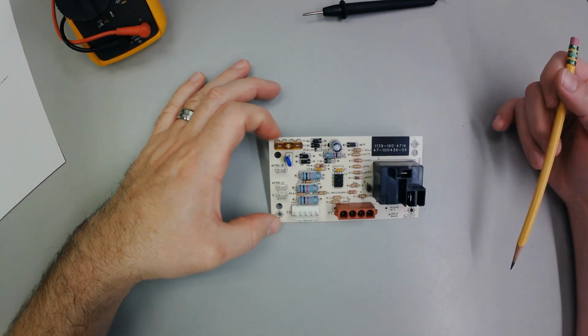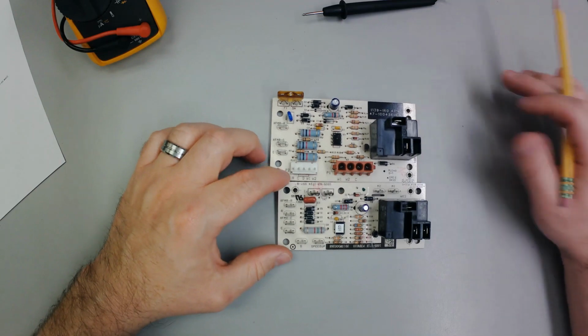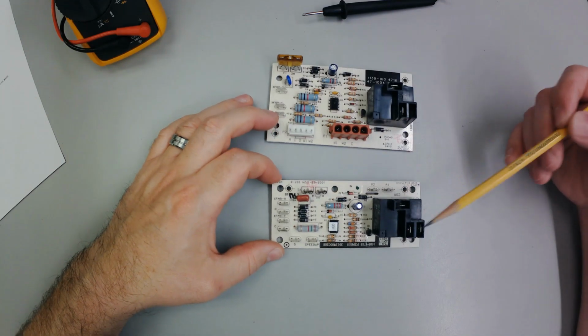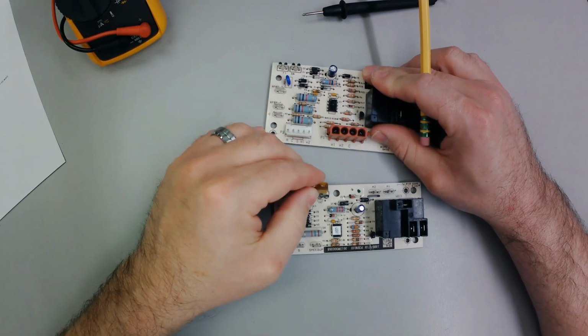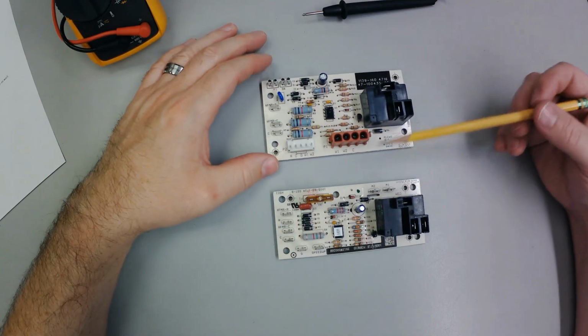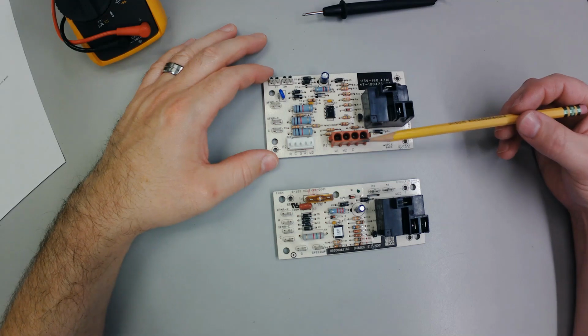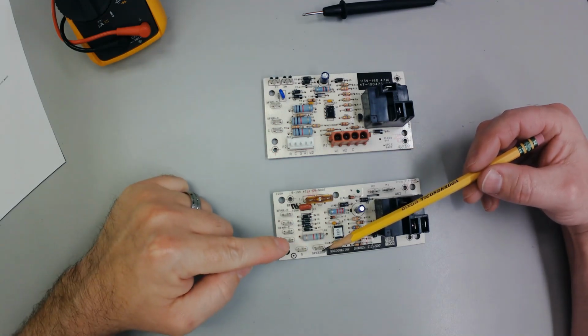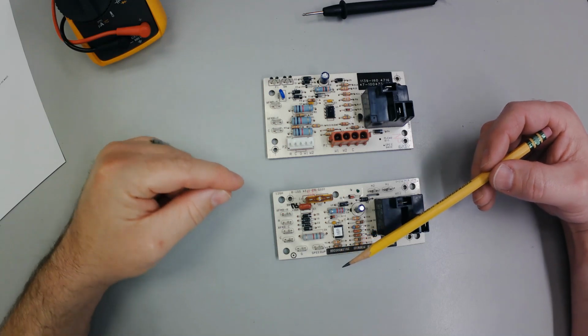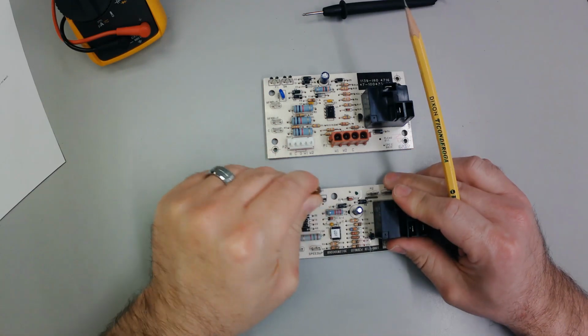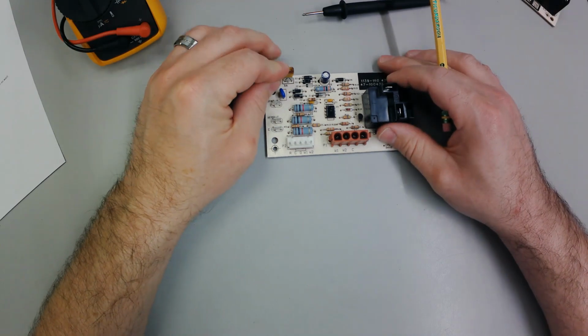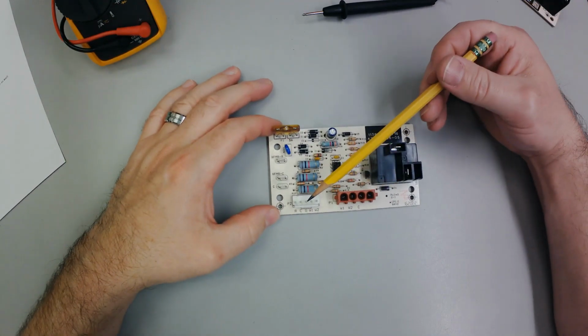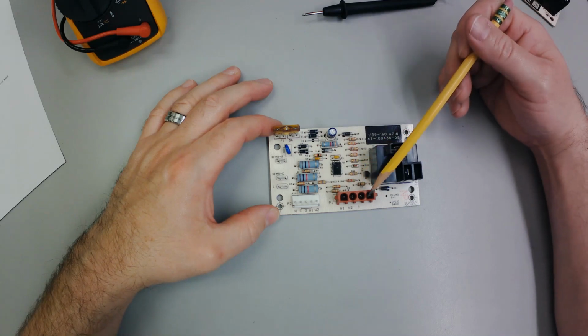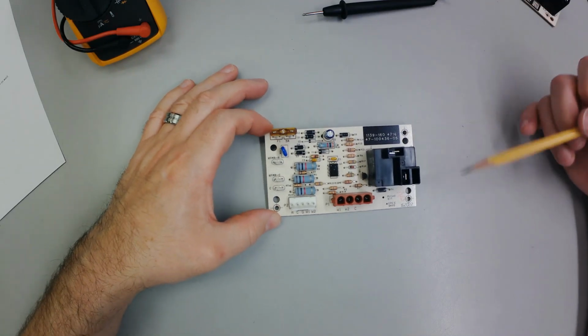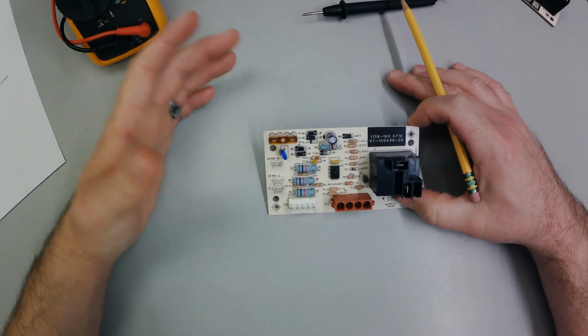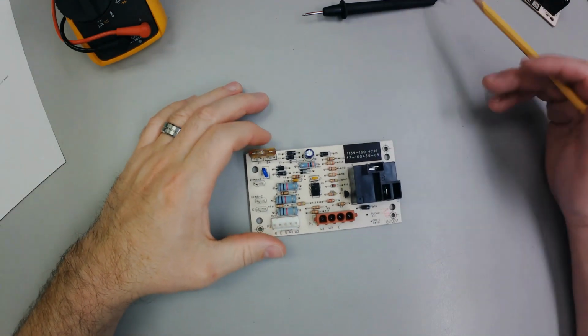The one thing that the Goodman board had, right? I'll flash it back real quick. On the Goodman, we got the relay, we got where the fuse goes, okay? But the Goodman board did not have these plugs soldered into it. We actually had some 1/4-inch male spades to connect to, and it was pretty much individual wires. So that's something different that this Rheem board does, but with the plugs, there is still a wire there, okay? So we've got a smaller plug and then this larger one where this red is, okay? So we'll take just a second and go through these and identify them real quick. Maybe you'll pick up something, right?